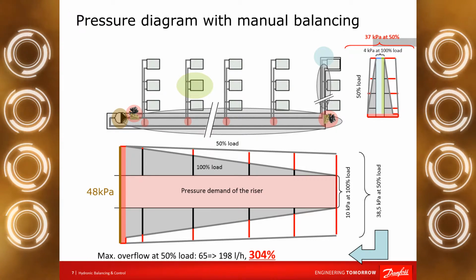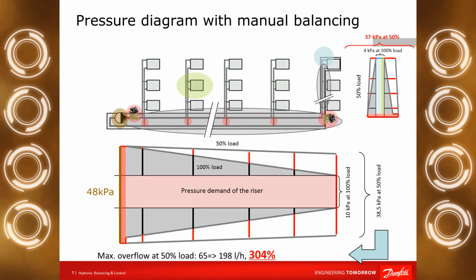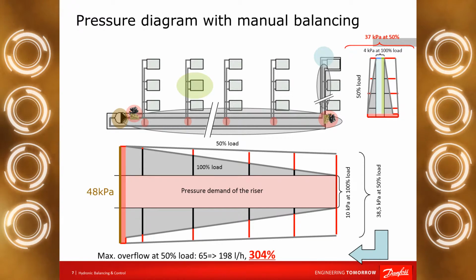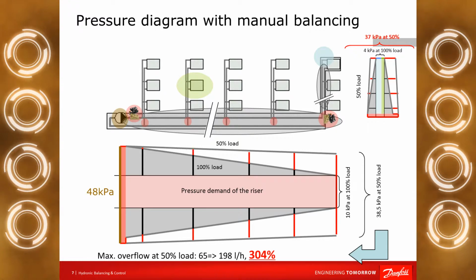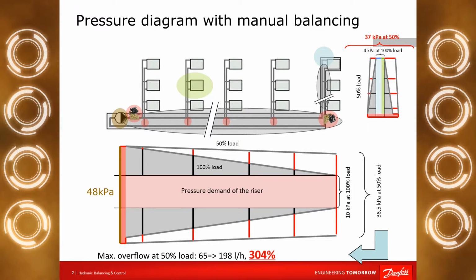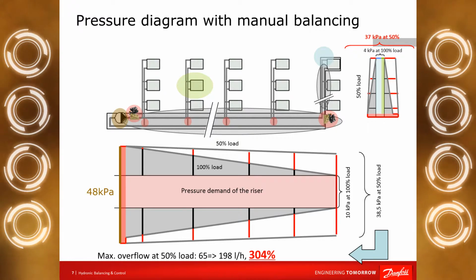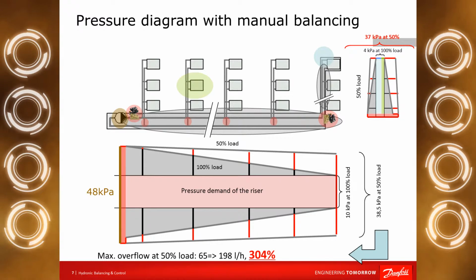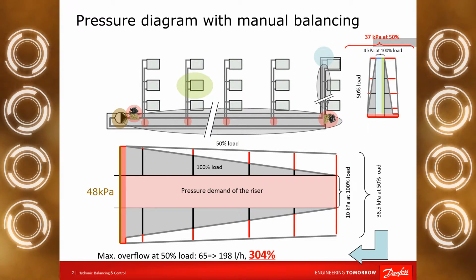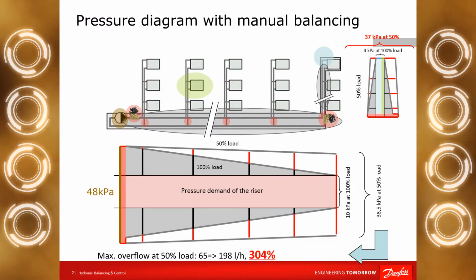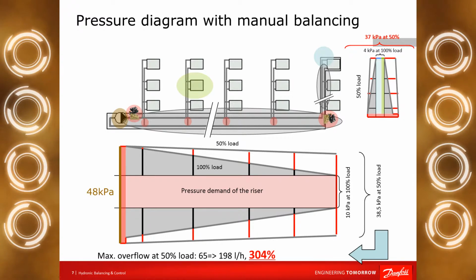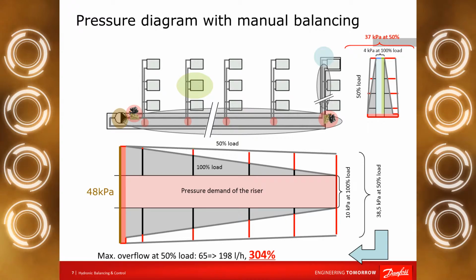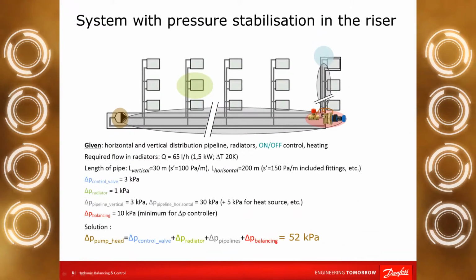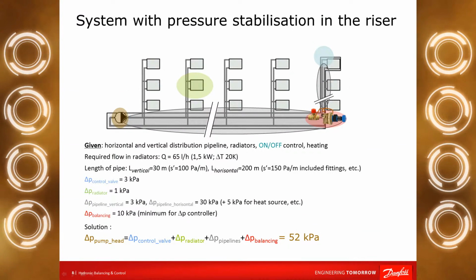What is the consequence of it? If we easily calculate what is the overflow through this radiator, the worst located radiator, more than 3 times more water will flow through this radiator. It's definitely a huge problem. Okay, let's see what will happen if we use a pressure differential controller in the bottom of the riser.